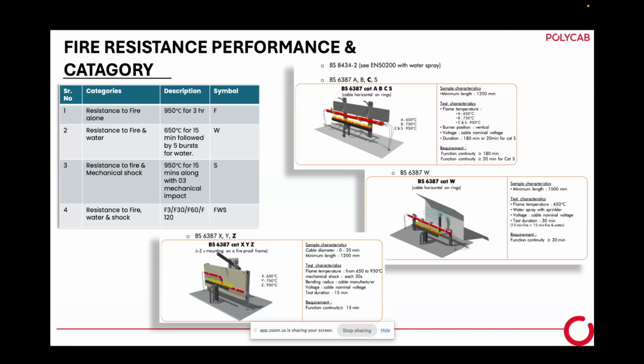Some customers want a cable resistant to fire and water, but not mechanical shock, since there is very little chance of that. For them, the category is W: 650-degree temperature for 15 minutes, followed by five bursts of water, is considered sufficient. This type of cable is called W.